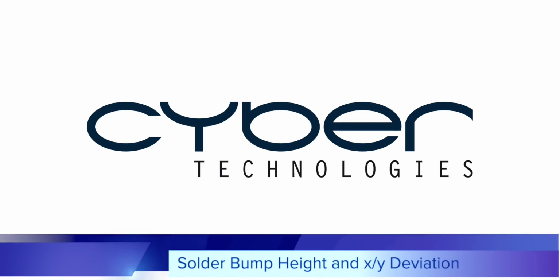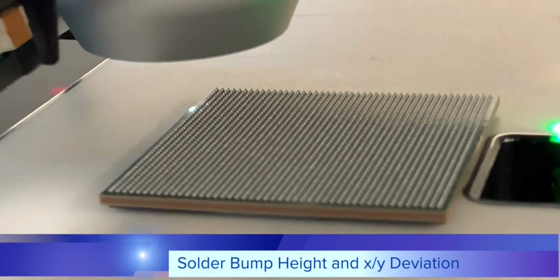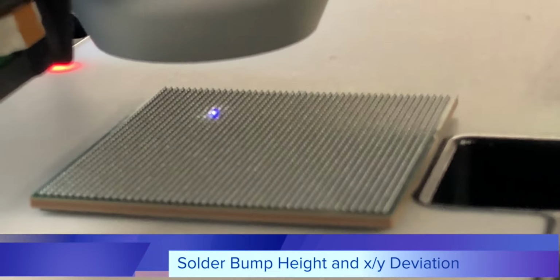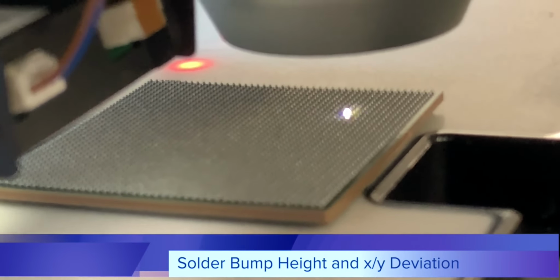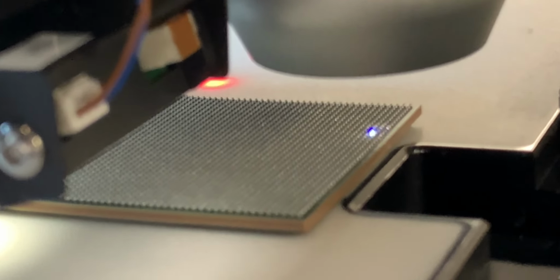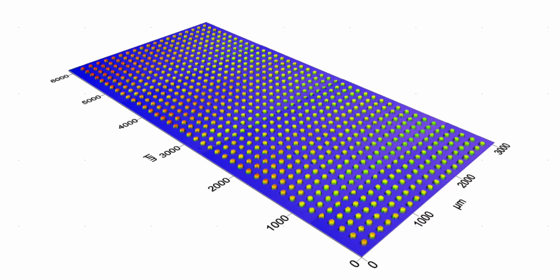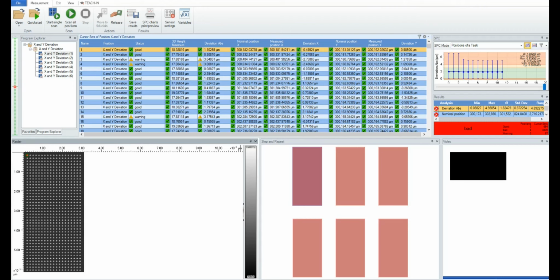Here we have a program that scans a grid of bumps, and we are interested in measuring the height and x and y deviations of each bump. The height of the bump is measured as the maximum height relative to the immediate substrate around it, which helps eliminate any warpage of the sample that would affect the measurement.